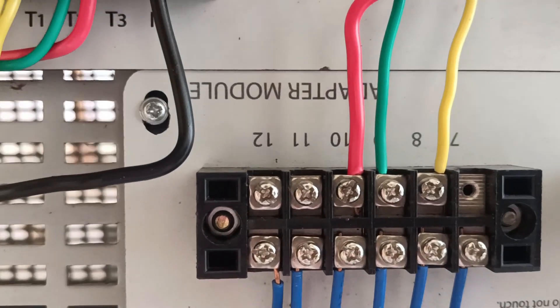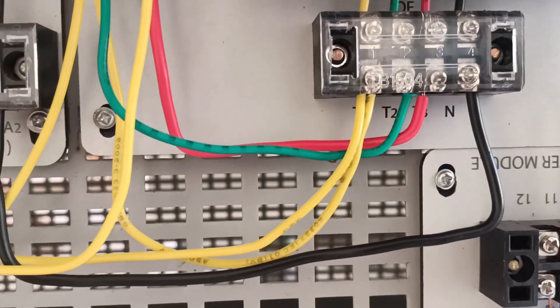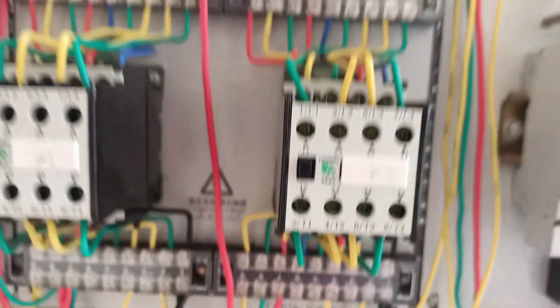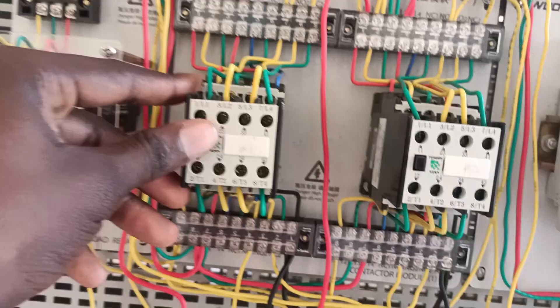Do the same for the second start button, that is for reverse. So the output pin 4 goes to the normally open of the second contactor, then loop it to the normally closed of the first contactor. The output of the normally closed of the first contactor goes back to the second contactor's energy coil A1, and the output of the normally open of the second contactor goes back to pin 3 of the reverse start button.